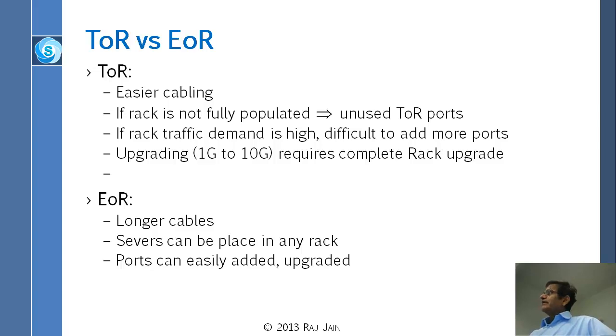The main negative of end of rack is longer cables. Now you have to manage the cables. Equipment is good, but the cables are long. Servers can be placed in any rack. That's another positive. Ports can be easily added, upgraded, and so on and so forth. So that's very good, right? You have to decide which one is cheaper or better for you.